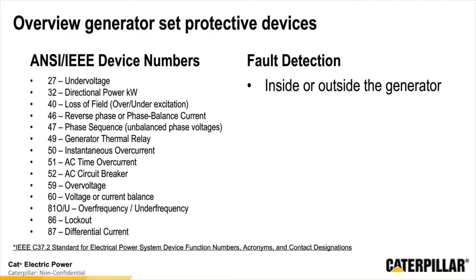So as we talk about the different devices that we have within a system, what we're looking at and considering is to be able to detect a fault wherever it occurs in the system. And a fault may be any different type of anomaly as we're doing our protection. As we talked about at the beginning, we're going to be mostly talking about short circuit faults within our discussion today. But depending on where the protective relay is within the system, we may be looking at inside the generator, which we would consider anything that comes up to the generator circuit breaker. Or, depending on if the relay is located in other portions, we may be looking at faults that are occurring outside the generator, or anything that's beyond the generator circuit breaker.